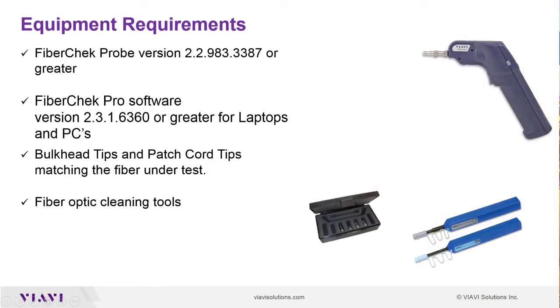Equipment Requirements. You'll need a FiberChek Probe version 2.2.983.3387 or greater, and FiberChek Pro software version 2.3.1.6360 or greater for laptops and PCs. You'll also need bulkhead tips and patch cords matching the fiber under test, and fiber optic cleaning tools.